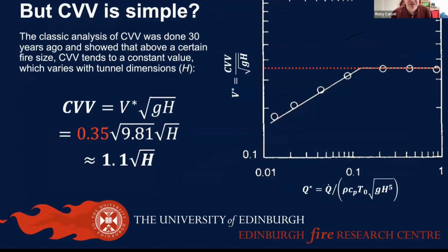If you go back 30 years, Oka and Atkinson came up with this graph on screen here. It basically shows that up to a certain fire size, there's a variation of ventilation velocity with heat release rate. Once we get to that bend point in the curve, we don't need more ventilation to control smoke from bigger fires. Very approximately, it's about 1.1 times the square root of the height of the tunnel, plus or minus error bars. But we generally design a tunnel with a safety factor anyway, so we don't need absolute precision in calculating the critical ventilation velocity.